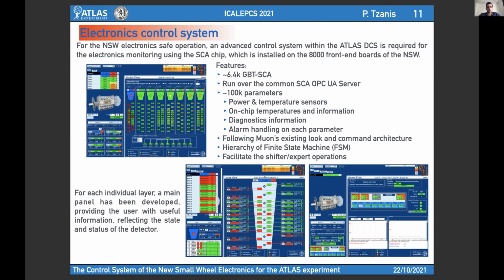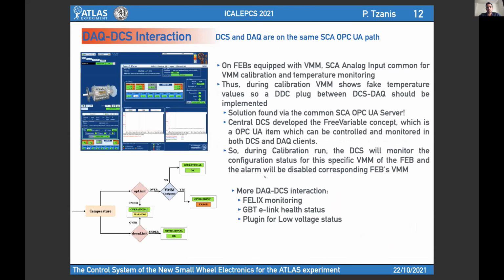As I said, it's the first time we have the configuration and calibration of the DCS on the same SCA OPC UA path. And there we had the case that on all the front-end boards equipped with the readout ASIC chip called VMM, the SCA analog input is common for the VMM calibration and the temperature monitor. Thus, during calibration, VMM shows fake temperature values, so a plugin between the DCS and the DAQ should be implemented.